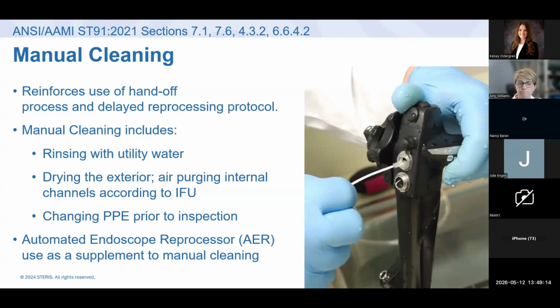Okay. PPE changes here also, from manual cleaning to when we're putting it in an AER, taking it out of an AER. Just as a point of note, air purges that are used as part of manual cleaning do not constitute drying. So we're going to talk about drying in a minute, but the air purge is just an air purge, okay? And then also automated reprocessing.